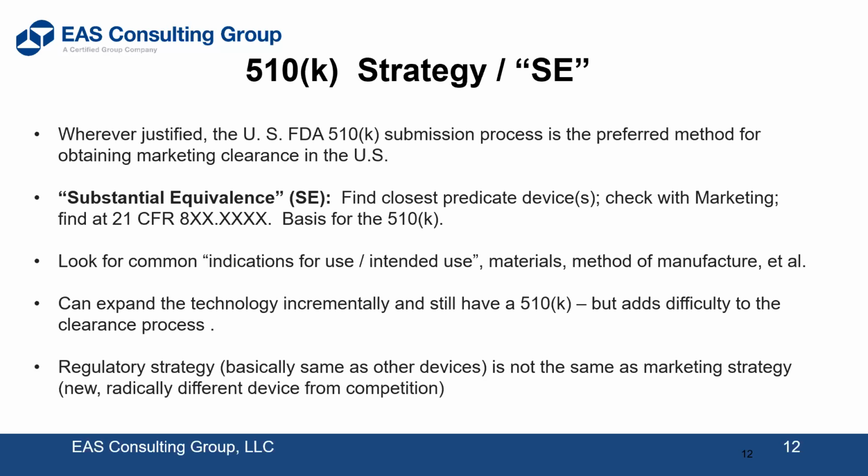Sometimes you find a product that has a 510K number, a K number: a K, then a year number, and then a sequential number, the year of submission to the FDA. Some of those devices never made it to market. They may have gotten a clearance from the FDA, but they never made it to market for whatever reason. That is not a valid predicate. In the past, the FDA didn't really check a lot of that apparently, but now they do.